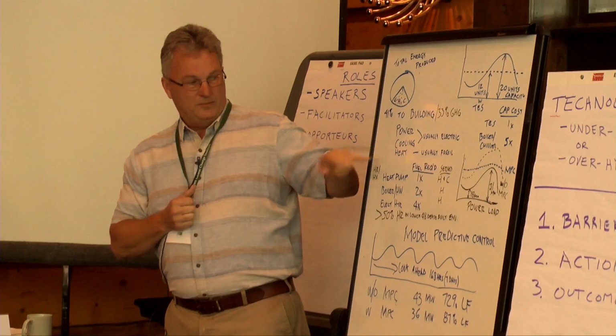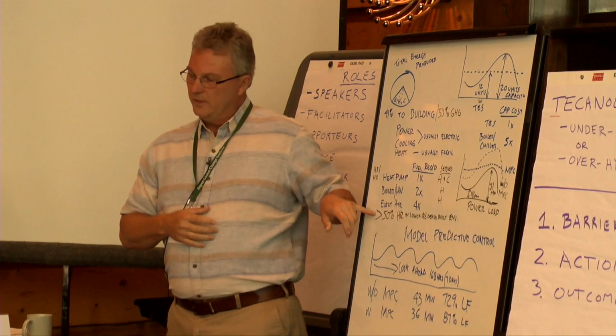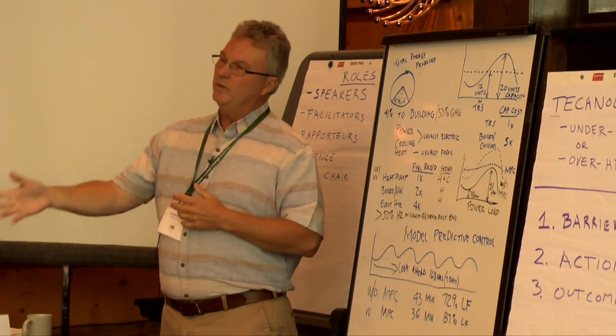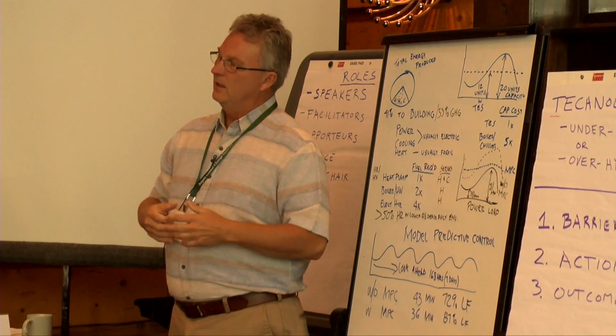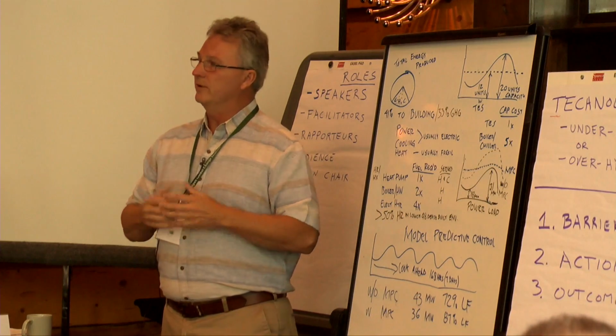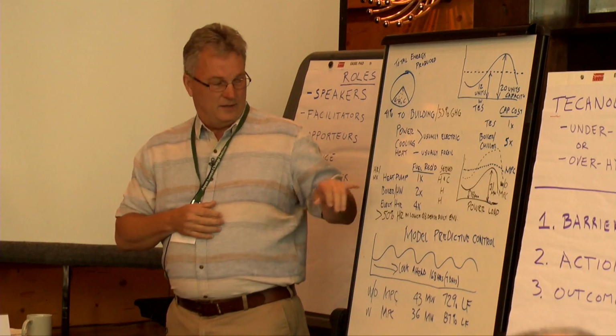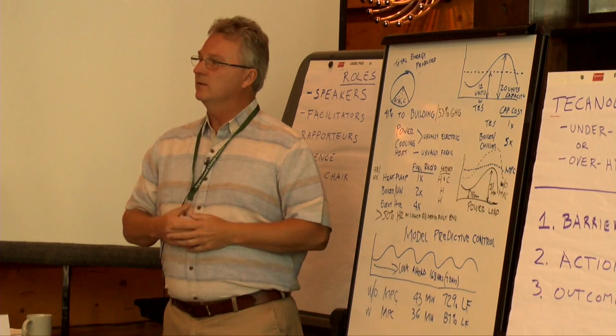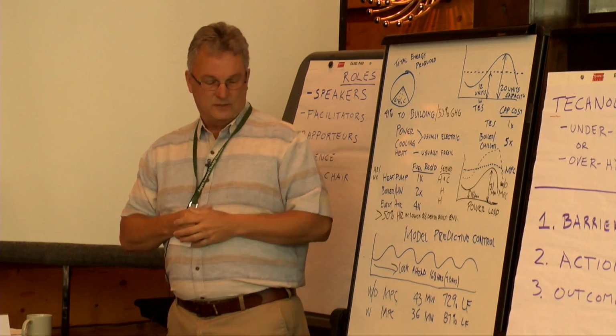So heat pumps, as the most efficient way to make heat, the most efficient way to use a heat pump is to first use recovered heat. So if you have a cooling process already going on, which is collection of unwanted heat and discarding it, well, if you can use that heat with your heat pump to provide heating and hot water for your system, then that's the best first use of a heat pump. The next best use is to extract heat from a water body or the ground in lieu of burning fossil fuel for all these reasons.